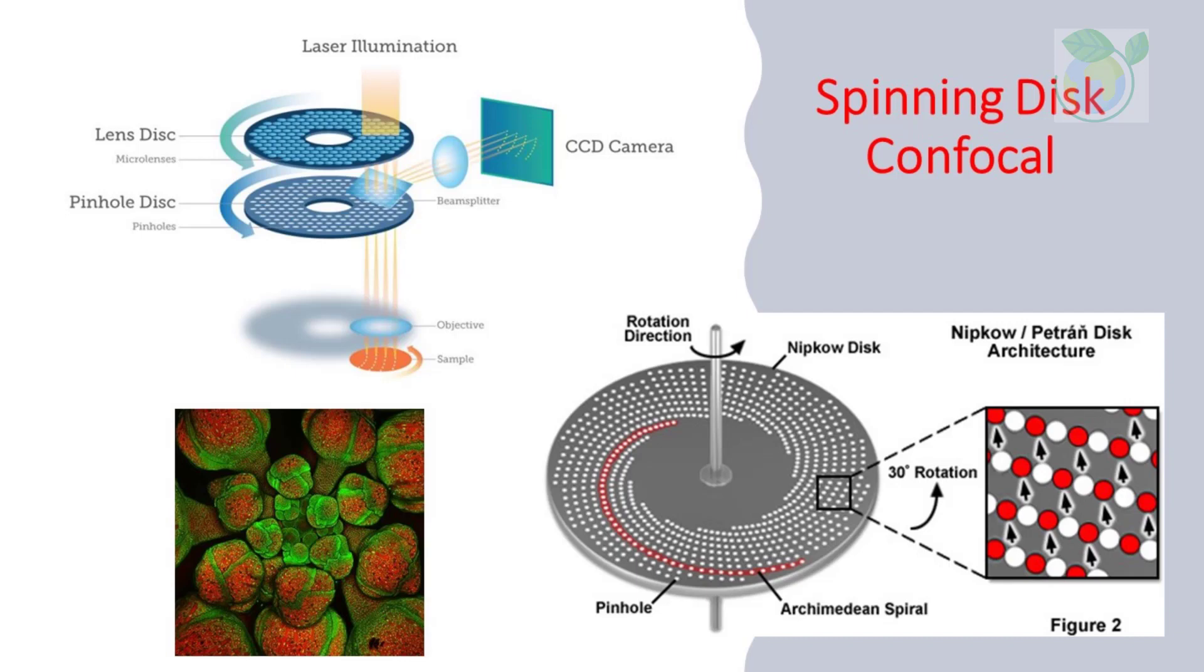Spinning disk, or Nipkow disk, confocal microscopes use a series of moving pinholes on a disk to scan spots of light. Since a series of pinholes scan an area in parallel, each pinhole is allowed to hover over a specific area for a longer amount of time, thereby reducing the excitation energy needed to illuminate a sample when compared to laser scanning microscopes. Decreased excitation energy reduces phototoxicity and photobleaching of a sample, often making it the preferred system for imaging live cells or organisms.